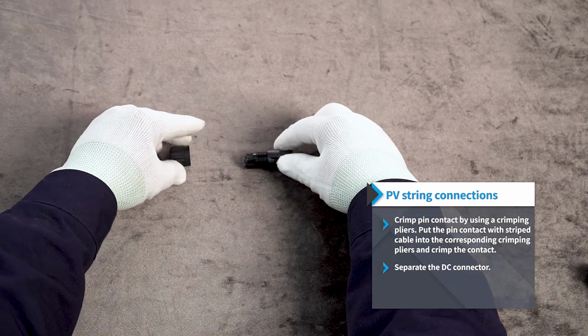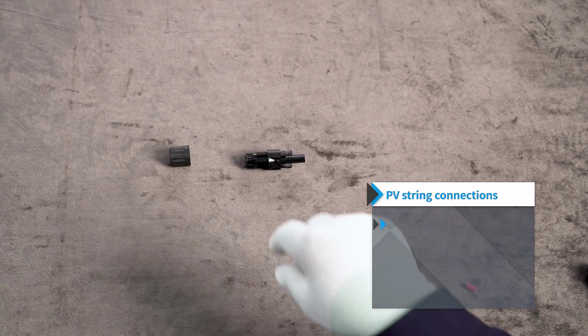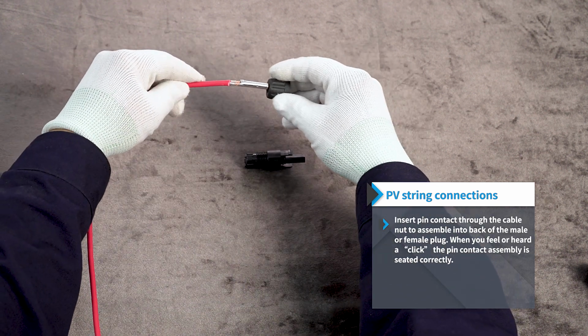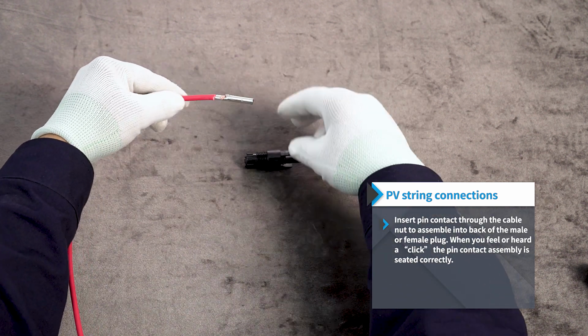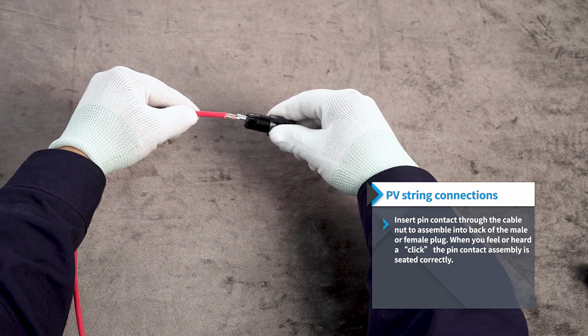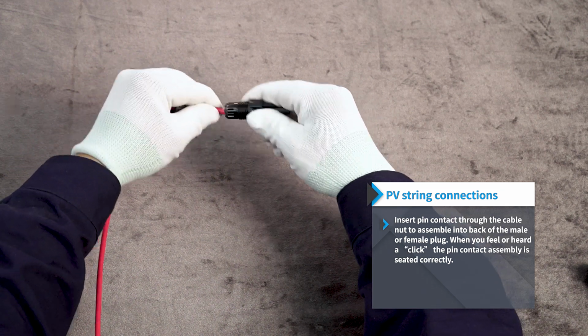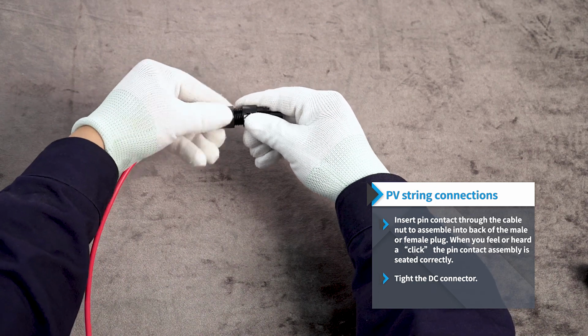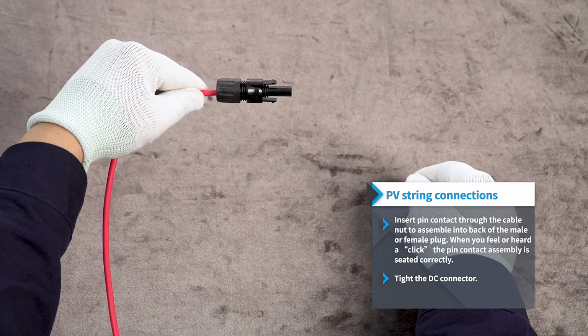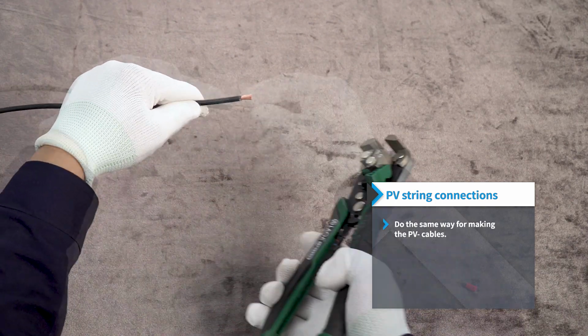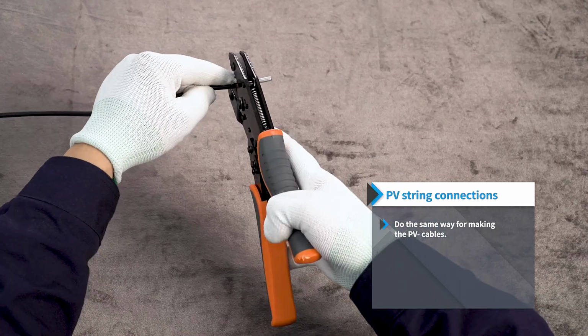Separate the DC connector. Insert pin contact through the cable nut to assemble into back of the male/female plug. When you feel or hear a click, the pin contact assembly is seated correctly. Tighten the DC connector. Do the same way for making the PV negative cables.